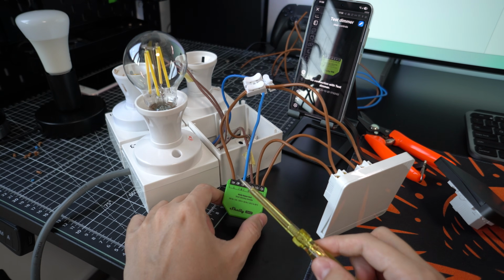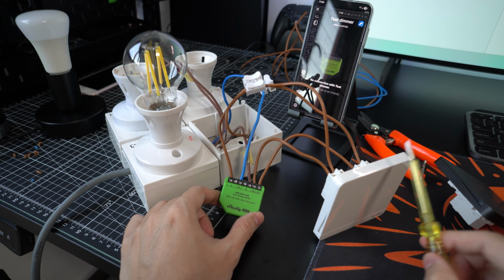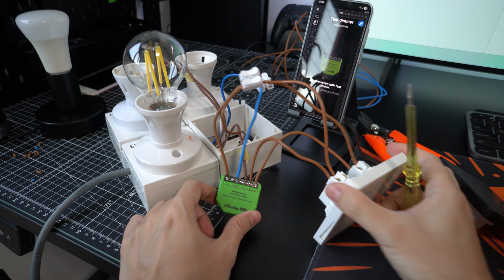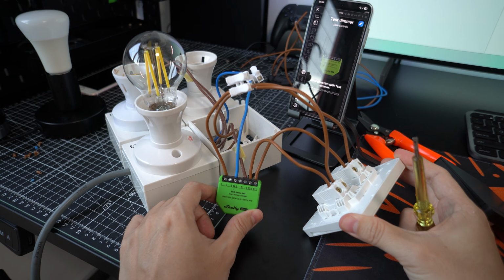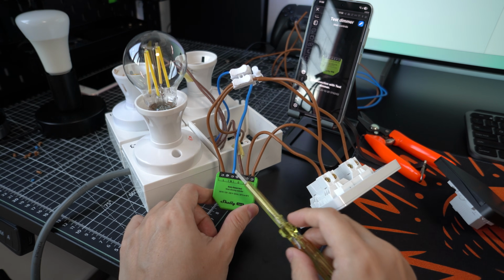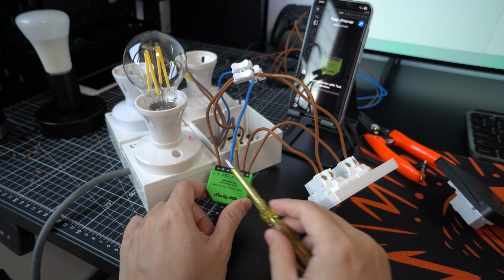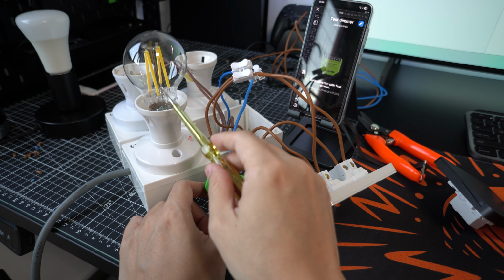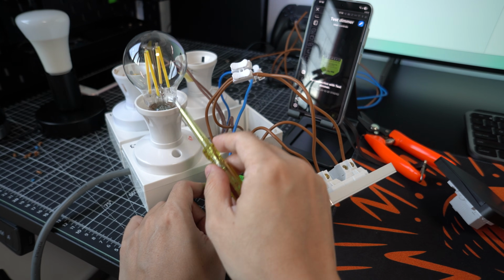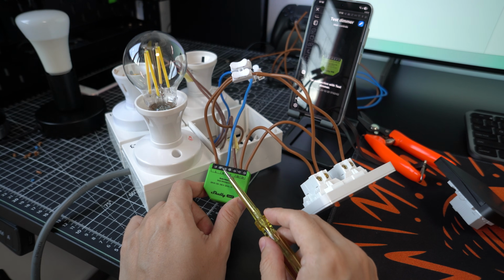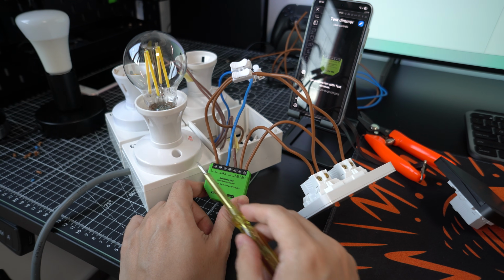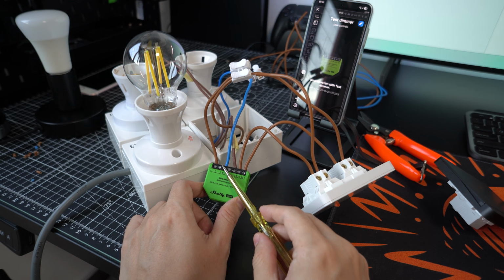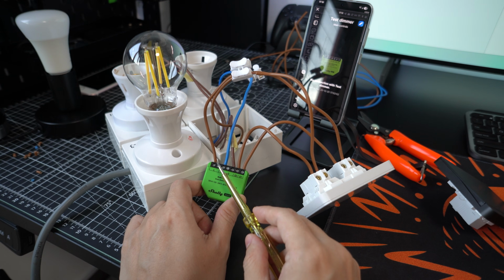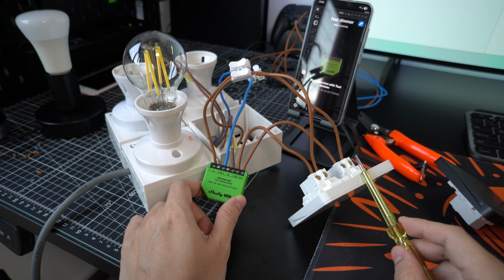Another interesting thing is you don't have to wire the neutral to the switch itself. You can see the switches don't have any neutral wire. So let's say you put this very near to the light, in the false ceiling. The light will always have a neutral. You can always loop the neutral over to the relay itself, then the neutral wire can stop there. You don't have to wire a neutral all the way to the switch end.